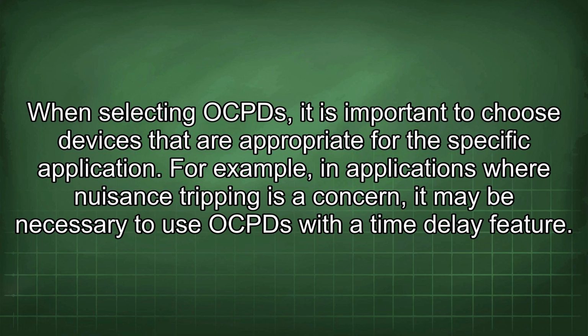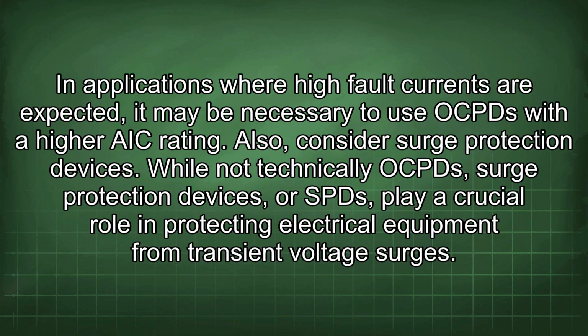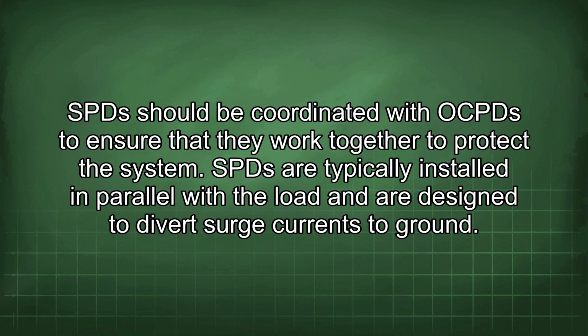For example, in applications where nuisance tripping is a concern, it may be necessary to use OCPDs with a time delay feature. In applications where high fault currents are expected, it may be necessary to use OCPDs with a higher AIC rating. Also, consider surge protection devices. While not technically OCPDs, surge protection devices, or SPDs, play a crucial role in protecting electrical equipment from transient voltage surges. SPDs should be coordinated with OCPDs to ensure that they work together to protect the system.